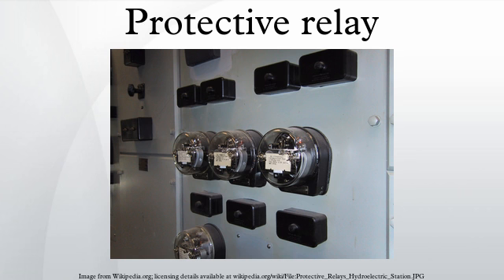A variant application of the attraction principle is the plunger type or solenoid operator. A reed relay is another example of the attraction principle. Moving coil meters use a loop of wire turns in a stationary magnet, similar to a galvanometer but with a contact lever instead of a pointer. These can be made with very high sensitivity. Another type of moving coil suspends the coil from two conductive ligaments, allowing very long travel of the coil. Induction disk overcurrent relay. Induction disk meters work by inducing currents in a disk that is free to rotate.